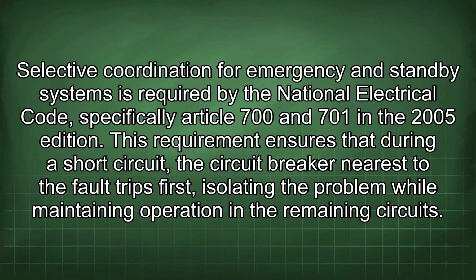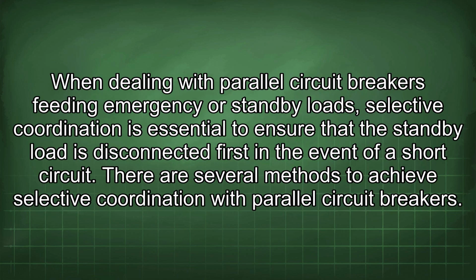Selective coordination for emergency and standby systems is required by the National Electrical Code, specifically Article 700 and 701 in the 2005 edition. This requirement ensures that during a short circuit, the circuit breaker nearest to the fault trips first, isolating the problem while maintaining operation in the remaining circuits. When dealing with parallel circuit breakers feeding emergency or standby loads, selective coordination is essential to ensure that the standby load is disconnected first in the event of a short circuit.